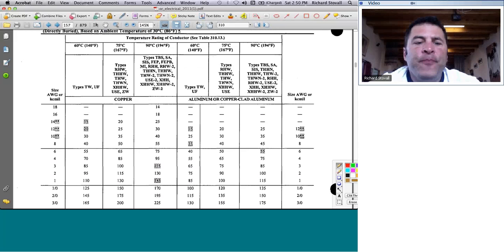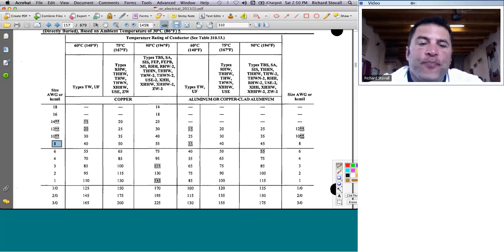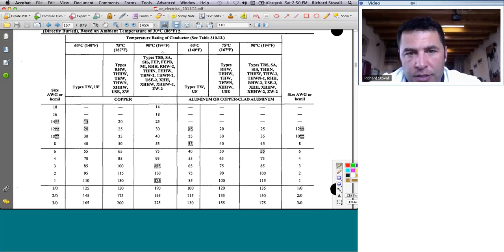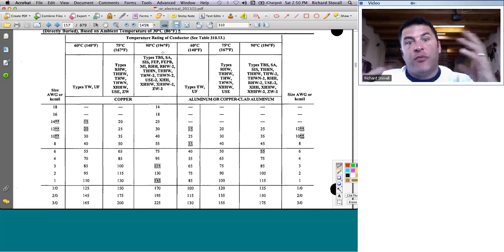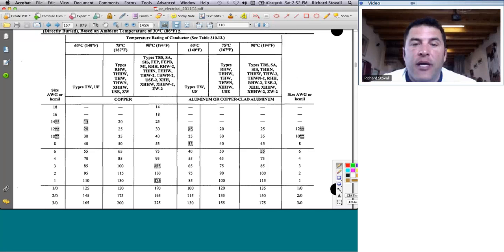So he's saying that our number eight, eight gauge, is good for any terminal type. Okay? And we may be using a conductor that has an insulation rating of 90 degrees Celsius, right? When we're sizing for ampacity of the conductor, the insulation around that conductor may be able to tolerate temperatures as high as 194 degrees Fahrenheit, and increased current increases temperature. So if you have an insulation that can handle more temperature, then you can handle more current.